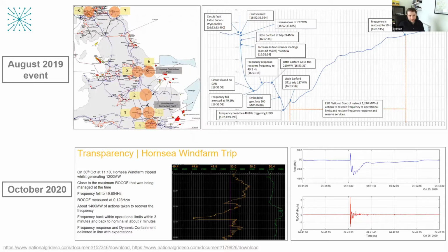So this has resulted in quite a complicated behavior, and ultimately, to save the wider system, about 10% of the GB system had to be tripped off. So it's over 1 million customers, but the system did recover. It made the headlines, and there were some very unpopular results from that in terms of transportation and so on. But the system did survive.